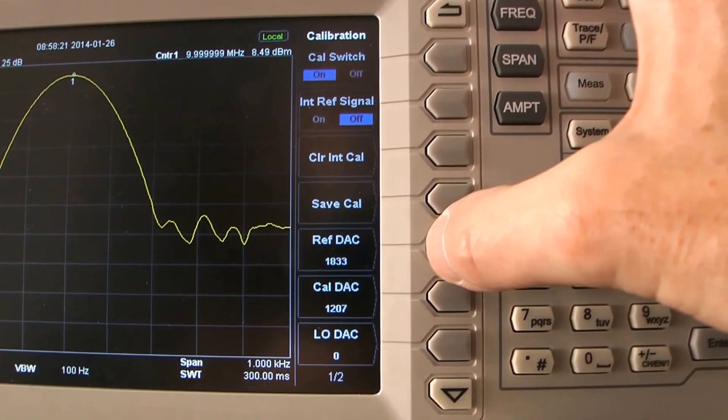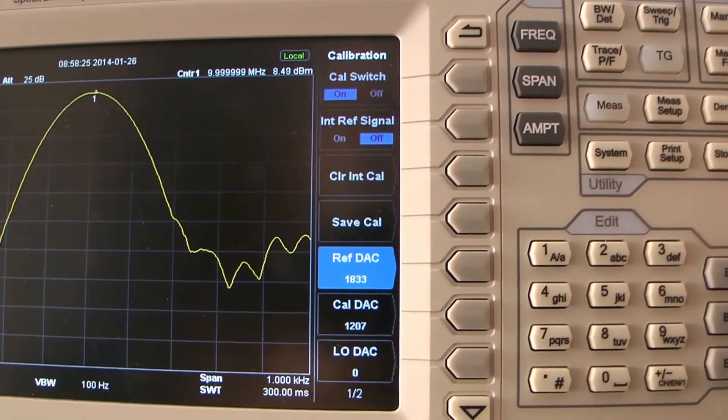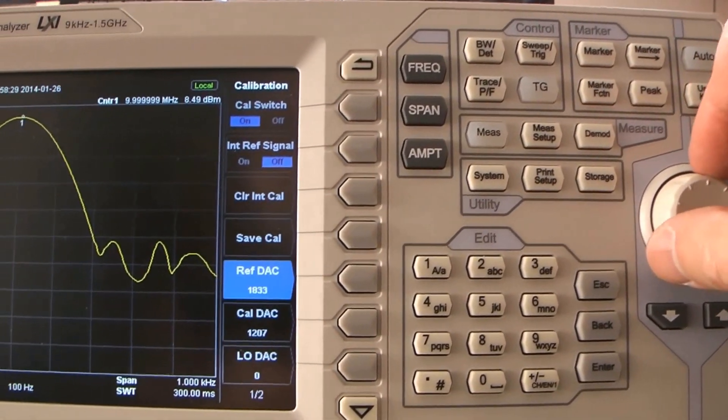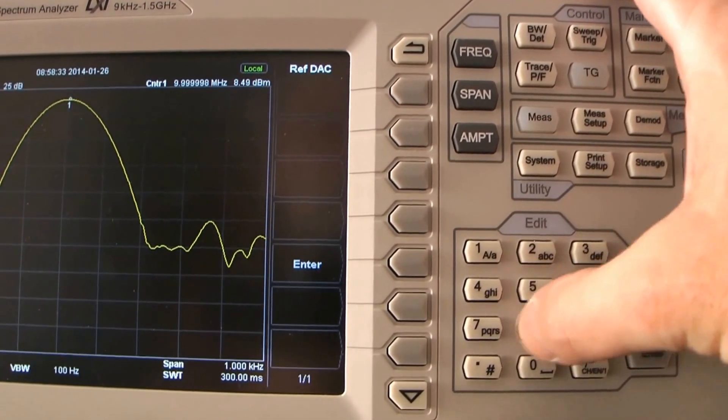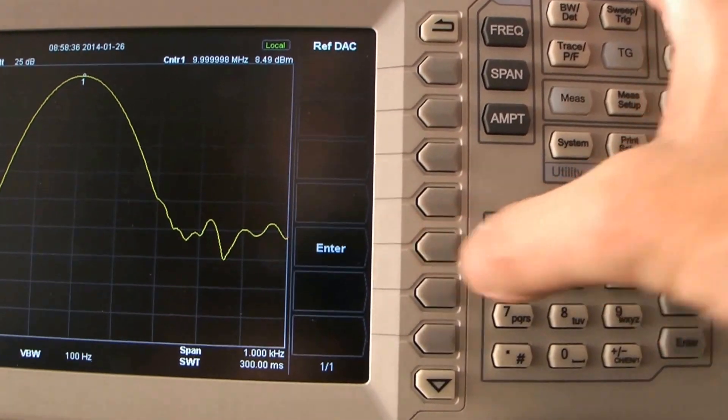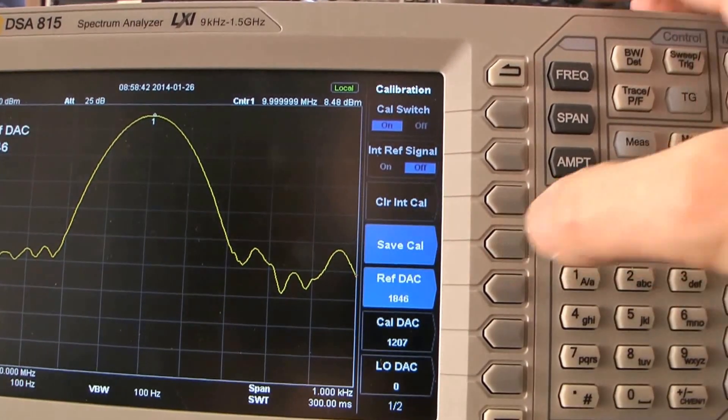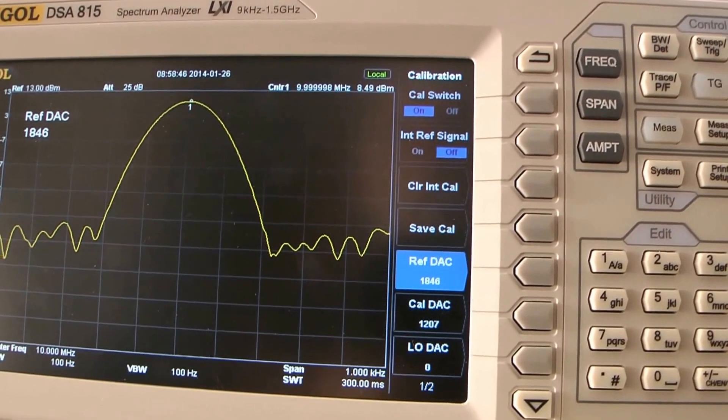So the way it works is you select that. You can't dial it, which is ridiculous. It has no effect. What you have to do is key in the value. So I'm going to put this back to 1846, which was the factory setting. And of course you wouldn't want to use this enter key. You would have to use this enter key. Alright, and then I can save that calibration.